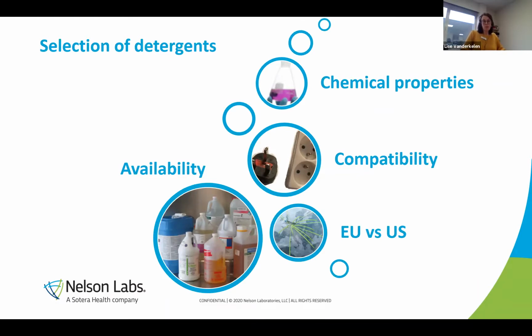And what is important for you as a manufacturer, you have to make sure that your device is compatible with that detergent. Your detergent should not degrade your device or destroy your device. It should be compatible. There are differences in the European and the US markets. For instance, in Europe, they prefer an alkaline detergent, whereas in the US, there is a preference for enzymatic detergents.